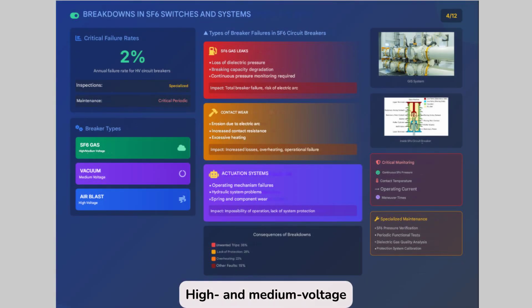High and medium voltage circuit breakers are key components in a substation, and their failure can lead to unwanted tripping, loss of protection, or service interruptions. Although they appear to be passive elements, their impact is critical both on technical operations and economic results, as a single failure can shut down the plant and lead to contractual penalties or losses due to undelivered energy. The annual failure rate for high-voltage circuit breakers is around 2%. This may seem low, but in plants without redundancy or in GIS systems, this percentage represents a high risk.